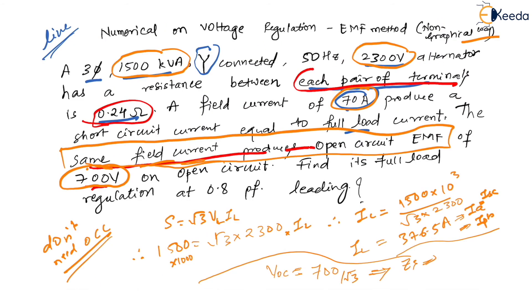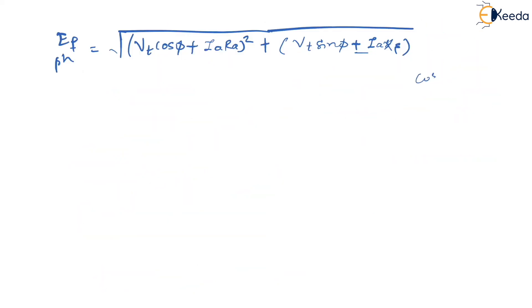Now we apply the EMF formula: EF = √[(VT·cosφ + IA·RA)² + (VT·sinφ ± IA·XS)²]. Here cosφ = 0.8, and sinφ = sin(cos⁻¹(0.8)) = sin(36.86°) = 0.6. The terminal voltage VT (phase) = 2300 / √3 = 1327.9 volts.